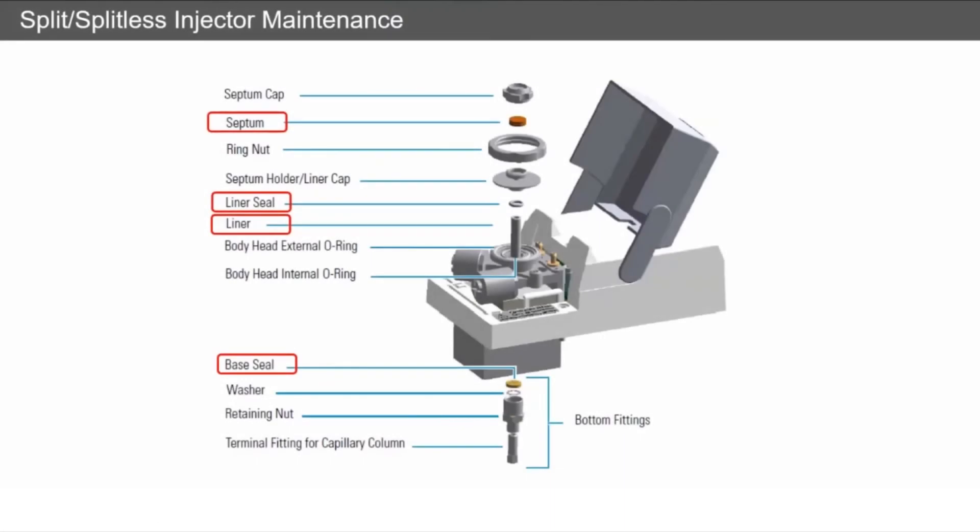Moving on to the injector maintenance, there is very little maintenance that needs to be done on an injector. Something like a septum, I'd recommend changing these on a daily basis.